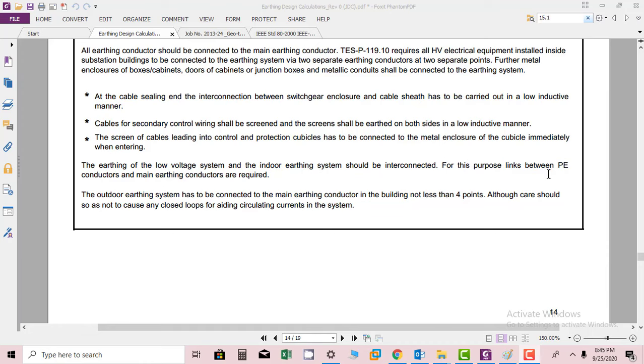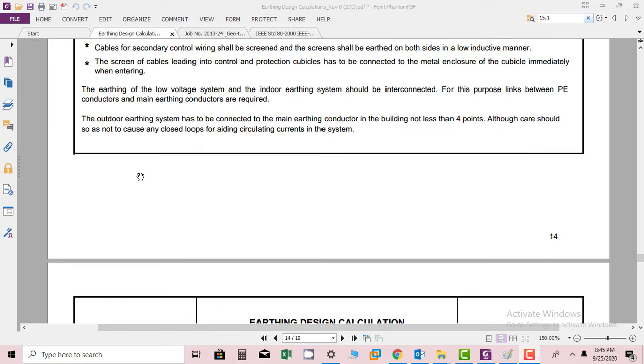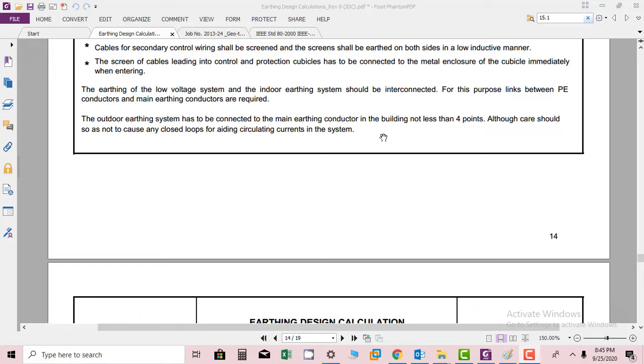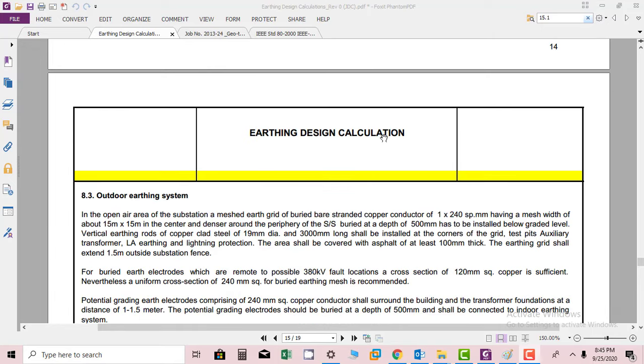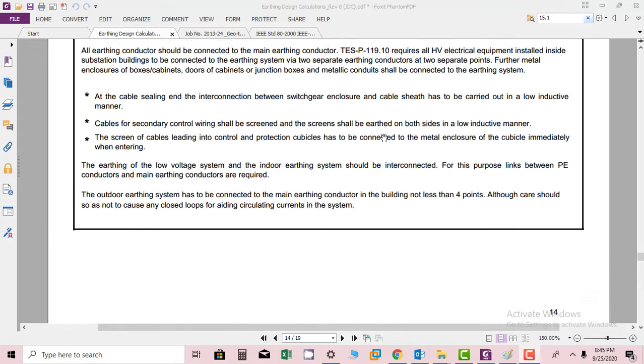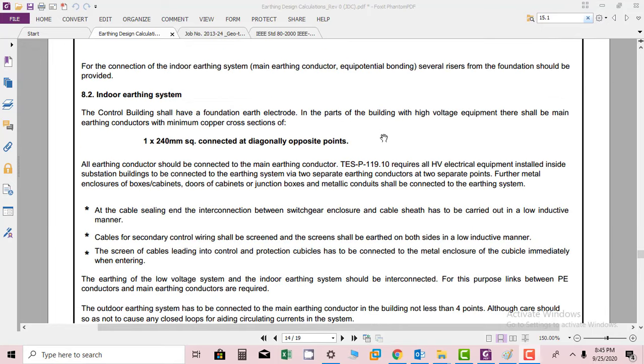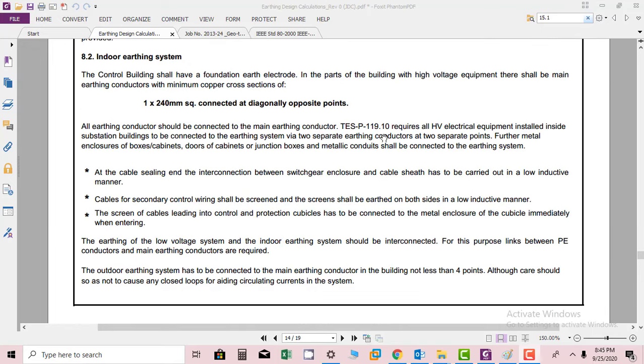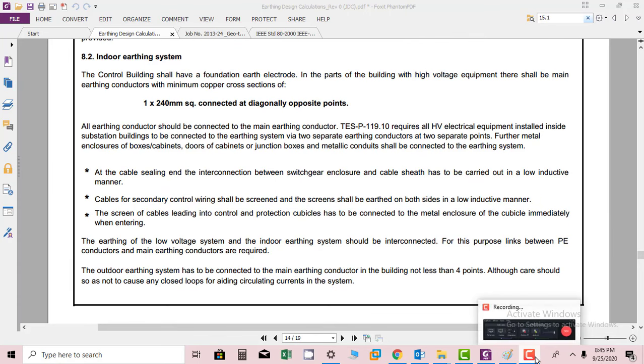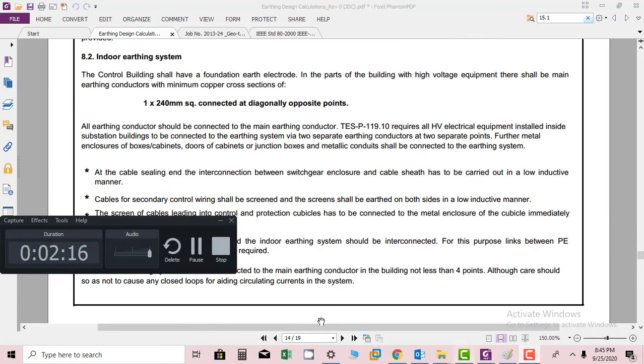The outdoor earthing system has to be connected to main earthing conductor in building at not less than four points. Care should be taken so as not to cause any closed loops for circulating currents in the system. So these were the instructions for indoor earthing system. Thank you very much.